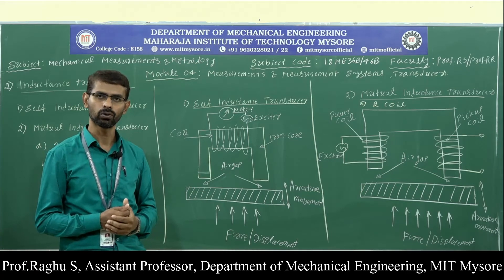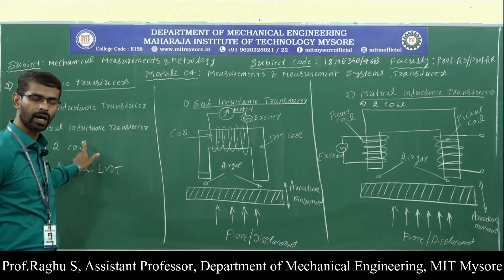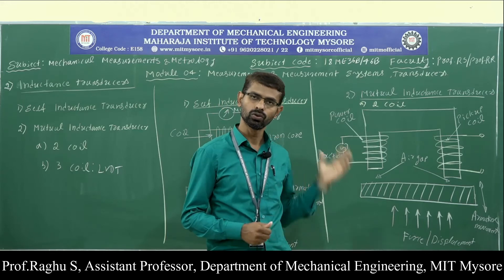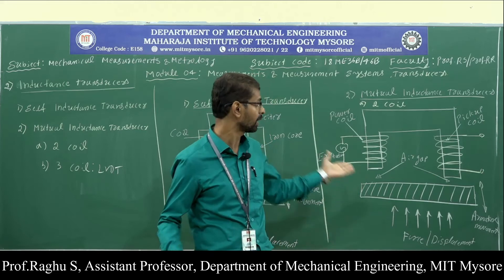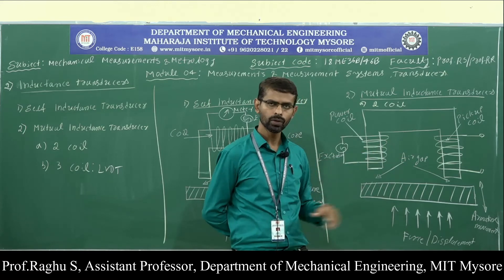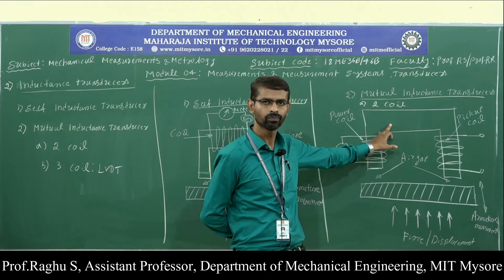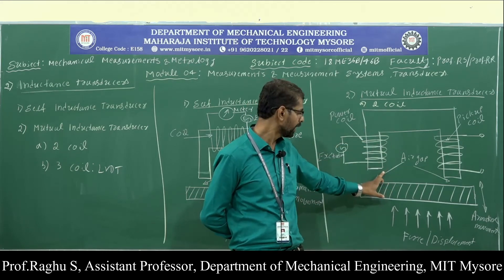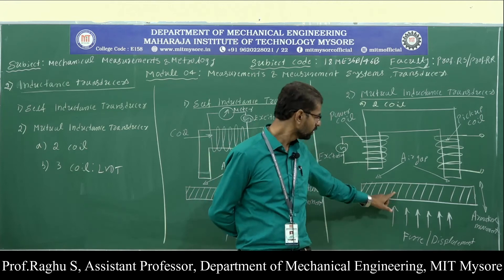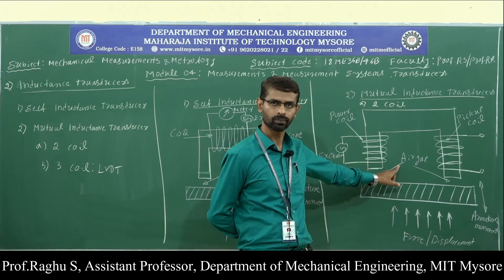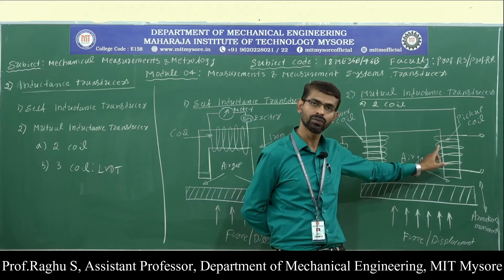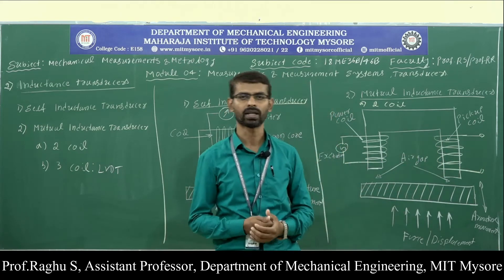In the mutual inductance transducer, we have two coils — a power coil and a pickup coil — wound on an iron core, with an armature and a small air gap. When mechanical displacement is applied to the armature, it moves closer to the iron core, and hence the mutual inductance of the pickup coil changes. The change in mutual inductance can be measured as mechanical displacement or force.